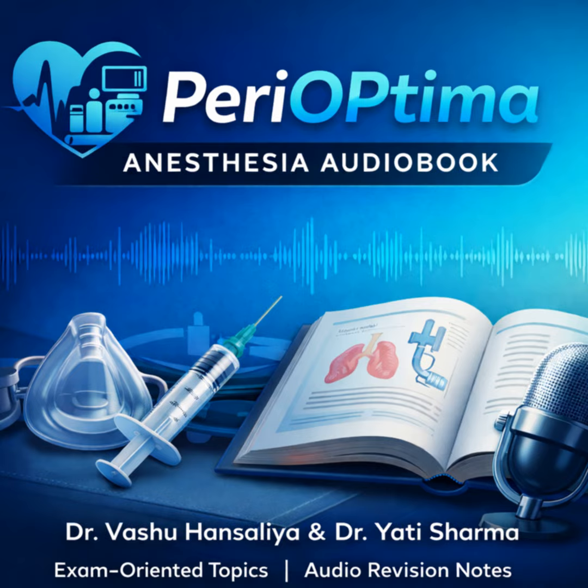This acts as a compliant storage volume. It accommodates the demands of breathing in and out, and crucially, it lets the anesthetist manually assist or control ventilation. Number 5. The adjustable pressure limiting valve, or APL valve. This is your exhaust valve. It vents excess gas, the volume of FGF that isn't being consumed, into the scavenging system. It stops excessive pressure from building up in the circuit, and its location is very important, usually on the expiratory limb. And finally, number 6.